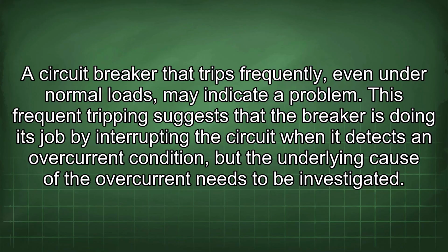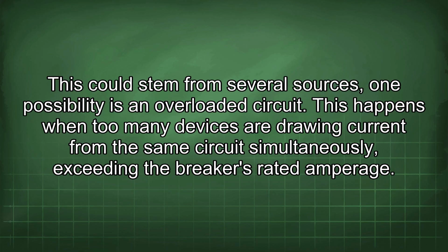A circuit breaker that trips frequently, even under normal loads, may indicate a problem. This frequent tripping suggests that the breaker is doing its job by interrupting the circuit when it detects an overcurrent condition, but the underlying cause of the overcurrent needs to be investigated. This could stem from several sources. One possibility is an overloaded circuit. This happens when too many devices are drawing current from the same circuit simultaneously, exceeding the breaker's rated amperage.